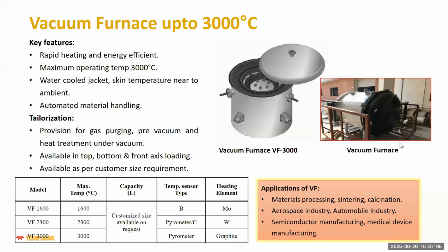What we have checked in our laboratory furnaces for 3000 degrees centigrade will also be applied in industrial furnaces. In industrial furnaces the sizes will be big, as per the customer requirement, and the same furnace can go up to 3000 degrees centigrade with different heating elements. For 1600 degrees centigrade, the heating element will be moly. For a 2300 degrees centigrade furnace, the heating element will be tungsten, and for 3000 degrees centigrade, the heating element will be graphite. The same configuration also applies for industrial applications.